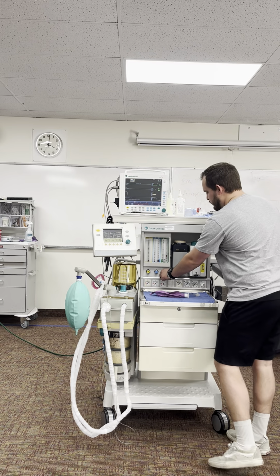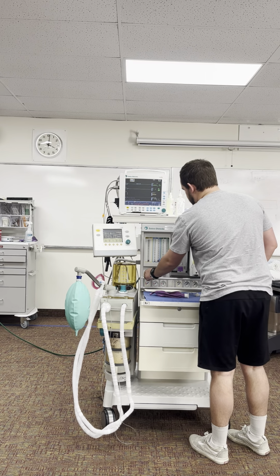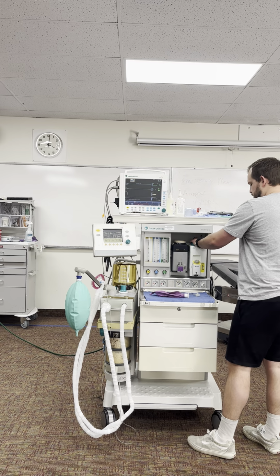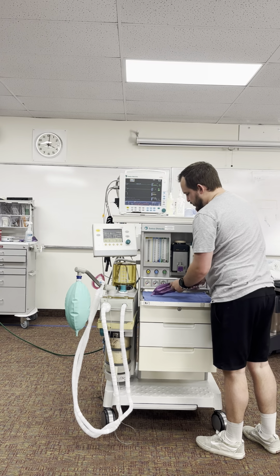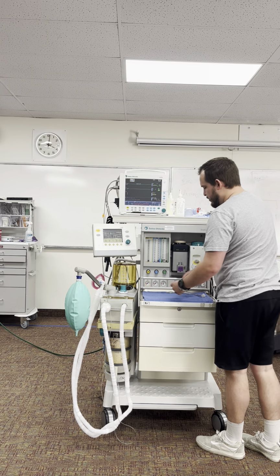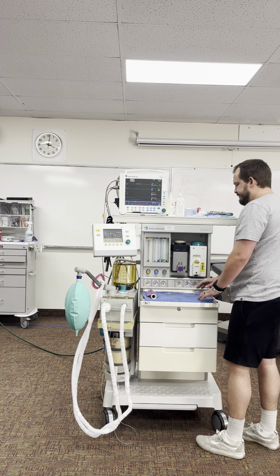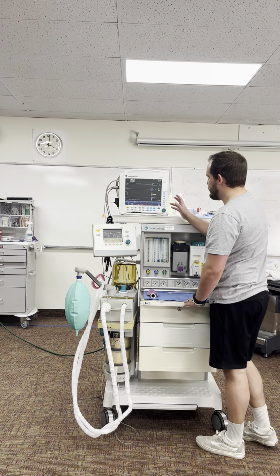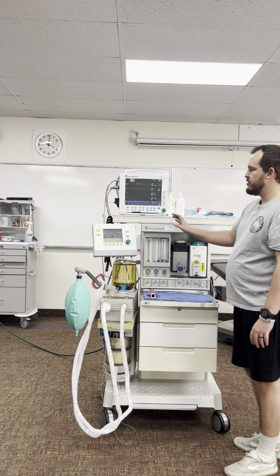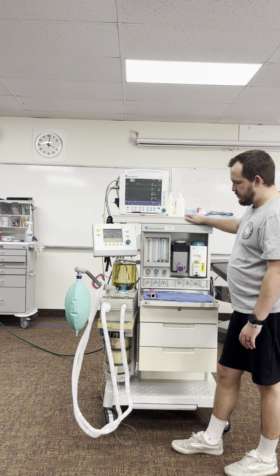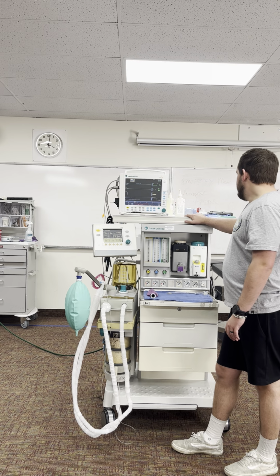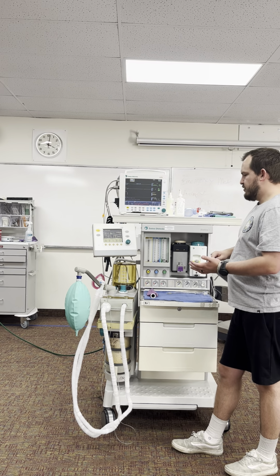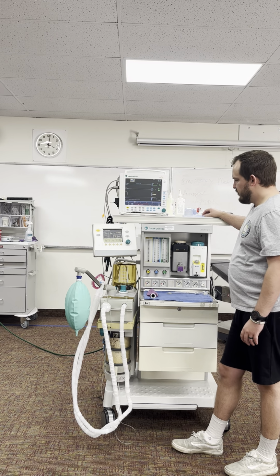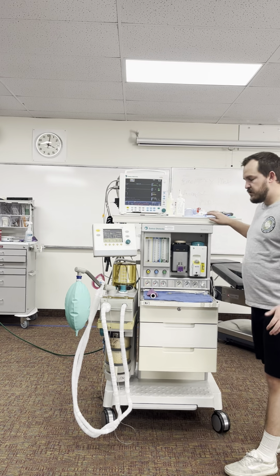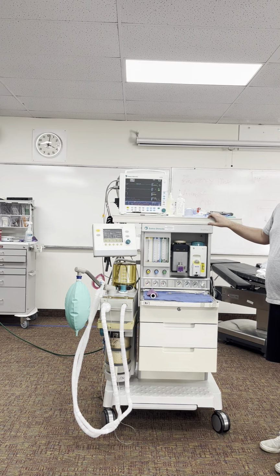Now I'm gonna go through, make sure that my flow meters are all off, make sure my vaporizers are off, make sure I have the appropriate equipment that I need for my patient, and any extra supplies I might need. Make sure my monitors are all set to the right parameters, and especially my ventilator. Make sure that is good and appropriate for the patient. One last time, I'm just gonna make sure my suction is good and appropriate, which it is. And so now I can document that my machine check is done, and I can go get the patient.